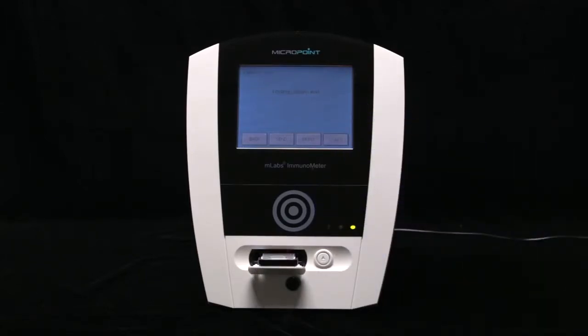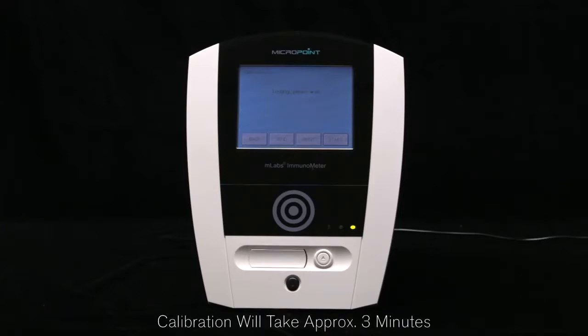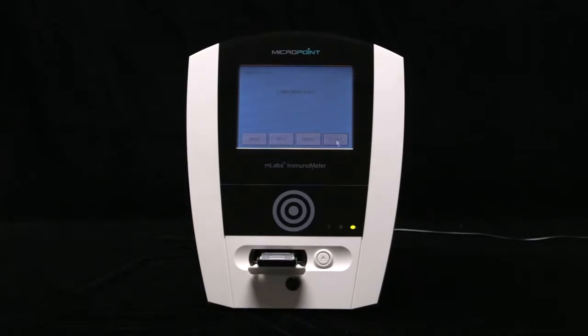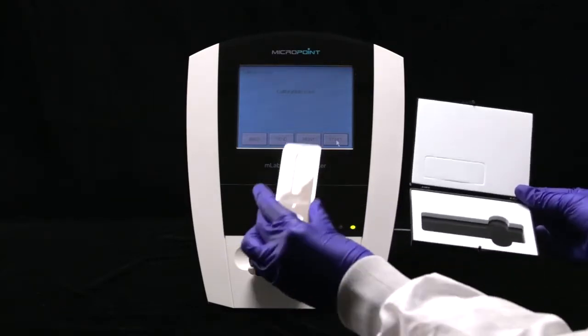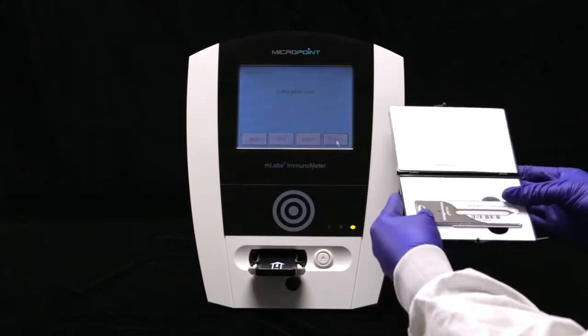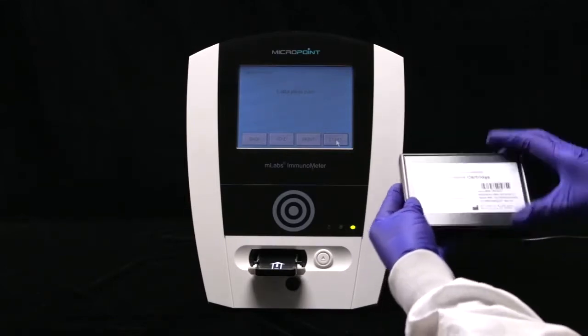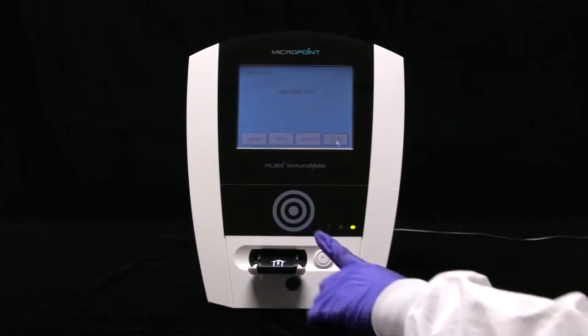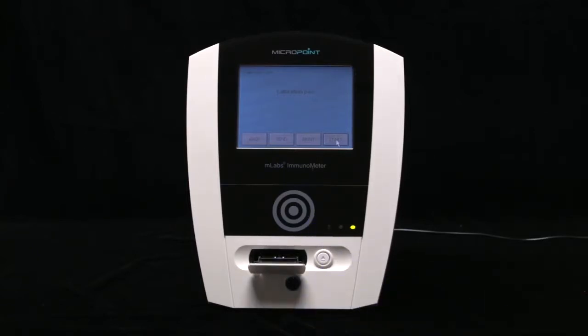The mLabs ImmunoMeter will perform calibration automatically. After calibration is completed, the mLabs ImmunoMeter will display either Calibration Pass or Calibration Fail on the screen. Once calibration is completed, the calibration cartridge will be ejected. Remove the calibration cartridge from the holder and put it back into the original box. Press the cartridge holder eject button to bring the cartridge holder back into the mLabs ImmunoMeter.